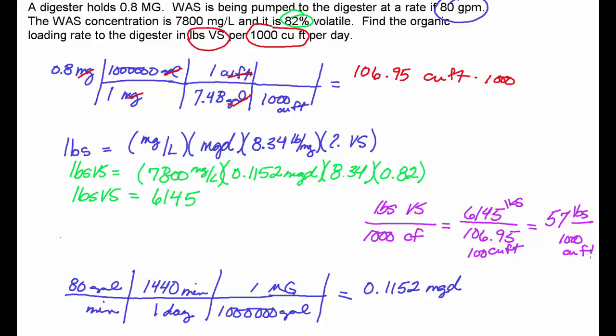A typical range for an anaerobic digester would be anywhere between 100 and maybe 350 pounds of volatiles per 1,000 cubic feet. So this is lightly loaded, but it's going to work just fine. Lightly loaded is okay.